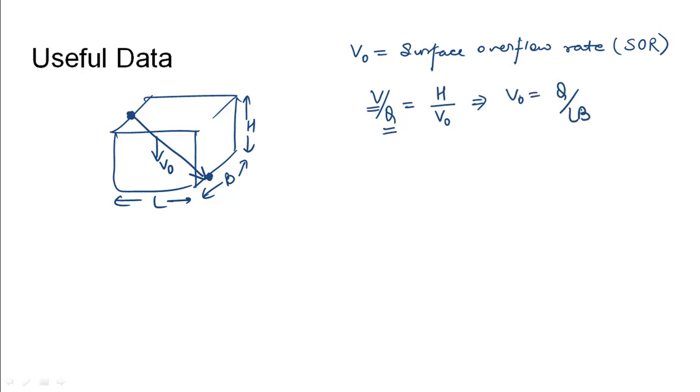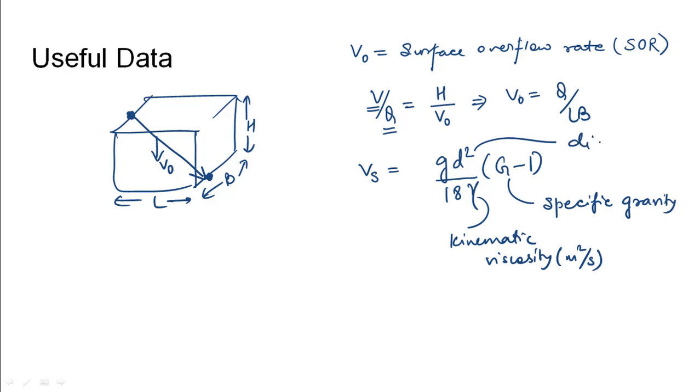Another concept is the settling velocity given by Stokes law: Vs = (g×d²)/(18γ)×(G-1), where G is specific gravity, γ is kinematic viscosity, d is particle diameter, and g is gravity. The efficiency of removal is η = (Vs/V₀)×100. If a particle has settling speed greater than or equal to V₀, its removal efficiency is 100%. If less, use this equation.